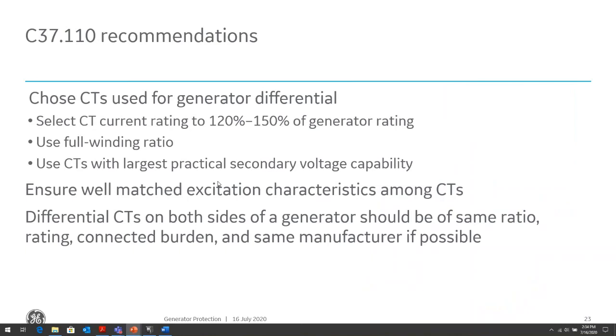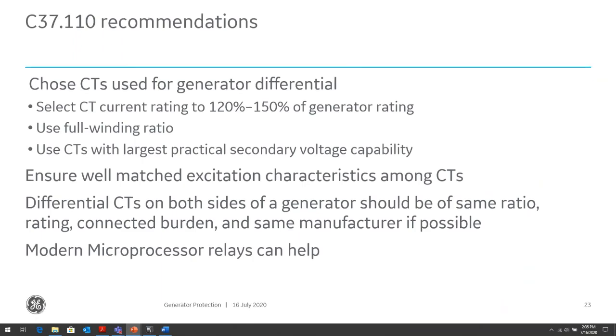This last point here: with differential, CTs on both sides of the generator should be the same ratio. Yes, but that is not so much true anymore when we talk about microprocessor relays, because microprocessor relays can handle differences between CT ratios, connected burdens and CT ratings. But to get the maximum operation out of the CT, you want to keep these within the same ratio, rating and connected burden, if you can. If not, then you have to adjust certain settings within the microprocessor relay to deal with these deficiencies. So modern microprocessor relays can help when you have these deficiencies.